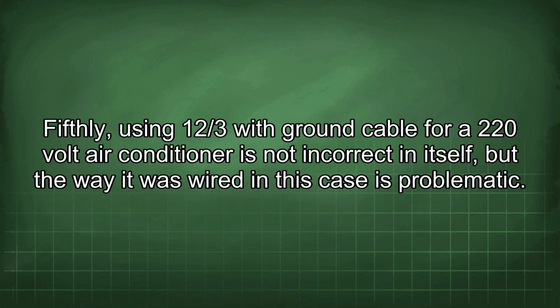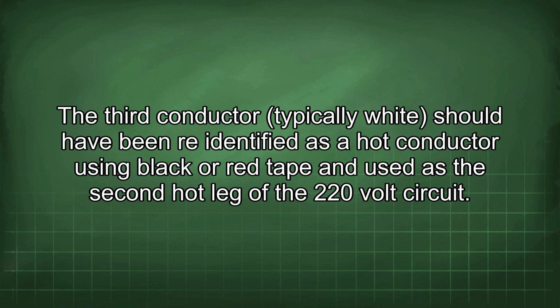Fifthly, using 12/3 with ground cable for a 220-volt air conditioner is not incorrect in itself, but the way it was wired in this case is problematic. The third conductor, typically white, should have been re-identified as a hot conductor using black or red tape and used as the second hot leg of the 220-volt circuit.